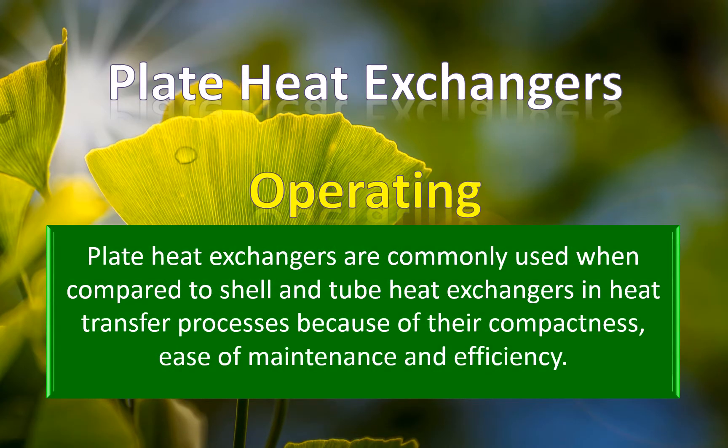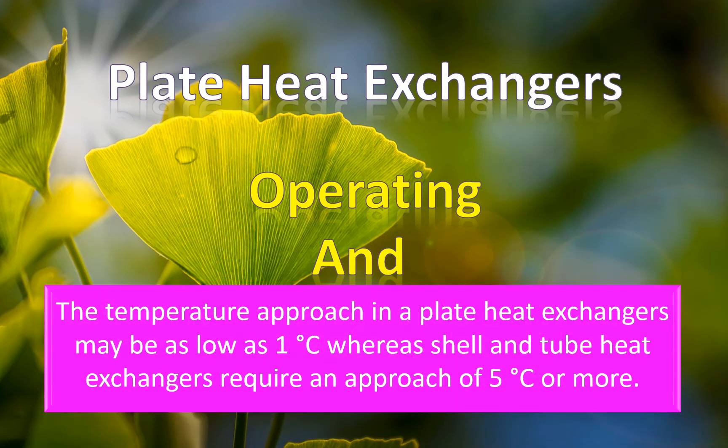Plate heat exchangers are commonly used when compared to shell and tube heat exchangers in heat transfer processes because of their compactness, ease of maintenance, and efficiency. The temperature approach in a plate heat exchanger may be as low as 1 degree centigrade, whereas shell and tube heat exchangers require an approach of 5 degrees centigrade or more.